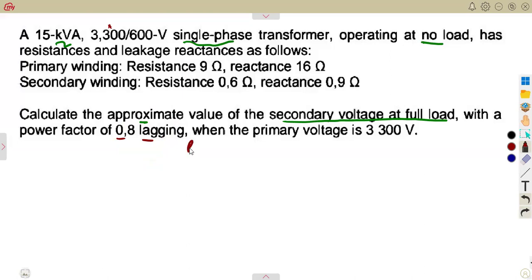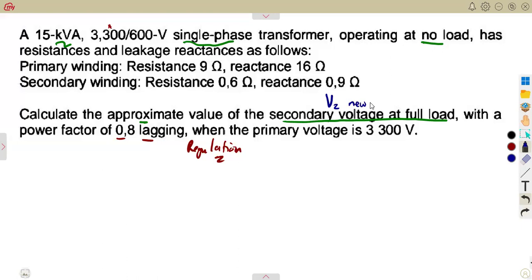They want us to calculate the approximate value of the secondary voltage at full load. When this lagging condition is considered, there is a voltage regulation involved. The secondary terminal voltage on load is V2 new, and it can be calculated if we are given the original voltage V2, which is 600 volts.